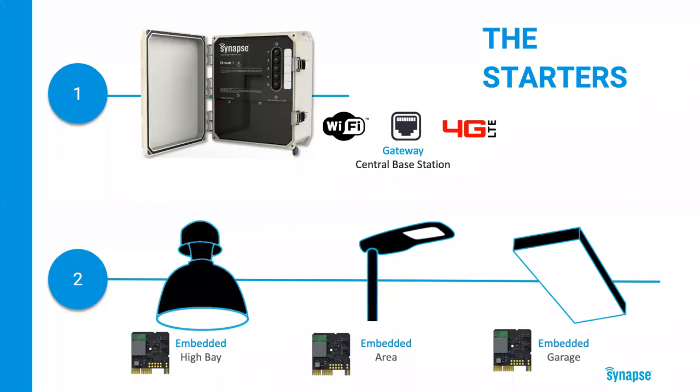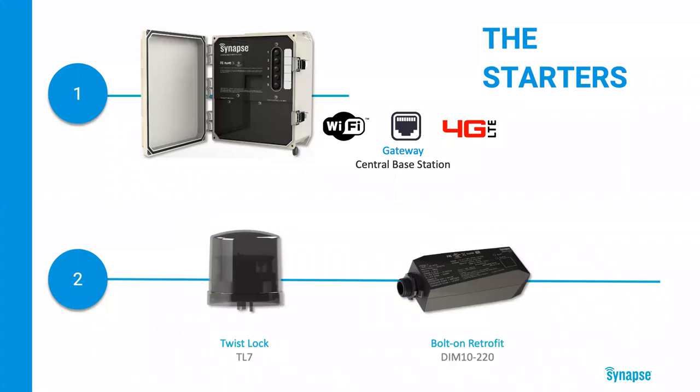We've worked to get our controls embedded in high bay, area, and parking structure fixtures from leading manufacturers so you can use Simply Snap in a variety of applications. For fixtures without embedded controls, we have solutions for those too. For fixtures with a NEMA socket or retrofit projects, our twist lock controllers are available in 277V and 480V with a built-in photocell and motion sensor integration, fitting into a standard 7-pin NEMA socket found on most parking or street lights. For LED retrofits, we have our IP65-rated DIM10-220 controller, which you can mount inside a pole or external to a fixture using a standard half-inch threaded nipple.